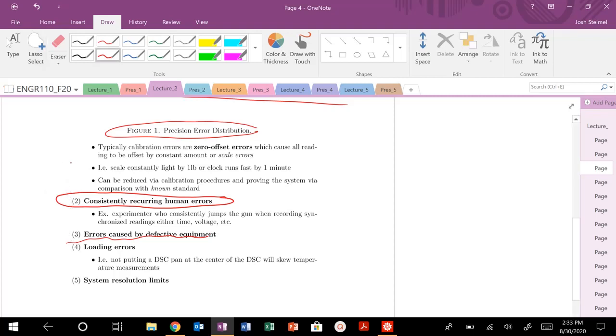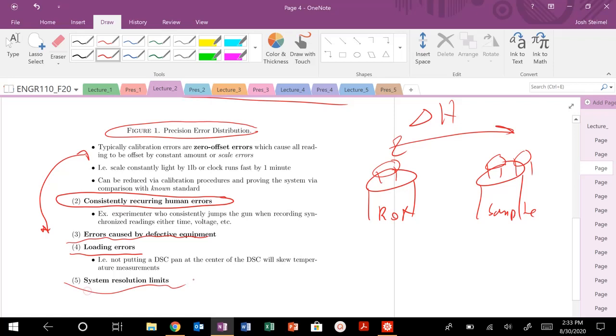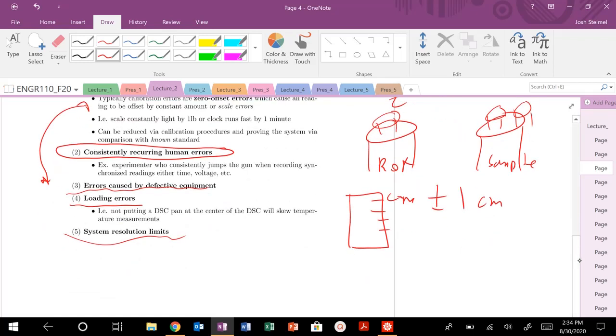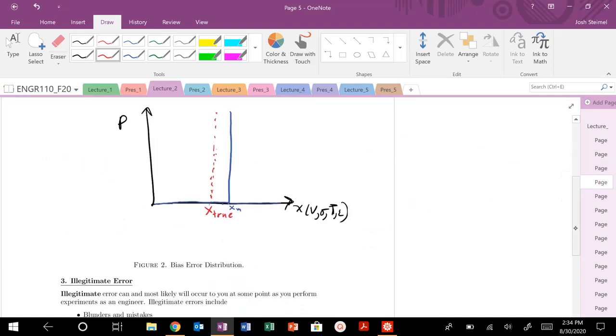Loading errors. In a differential scanning calorimeter, you have a reference pan and a sample pan stage. If you don't place them exactly at the center here, and you have it slightly off-tilted, that could change, when you're measuring heat flow, that delta H. That can skew your measurements. And then, of course, system resolution measurements. If I have a ruler, and the tick marks are centimeters, my bias error for this device is going to be plus or minus, I can't read better than plus or minus one centimeter. Some might do 0.5 or 0.3. I like to be very conscious in my life and in measurements in general.